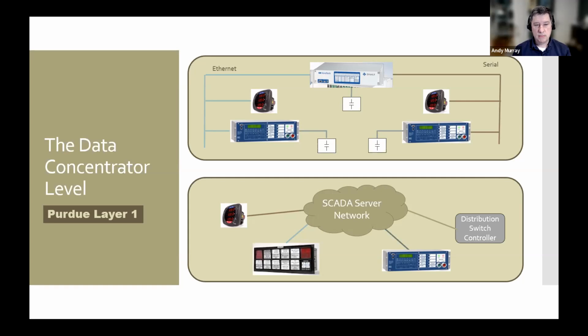Another thing that we see more and more now is, because these smart devices have communications built into them, you may not need that central data concentrator. You may have these devices connected directly into the network by Ethernet or fiber. And then your SCADA system can just monitor them directly, without that intermediate data concentrator that we were used to seeing in a more traditional SCADA setup.